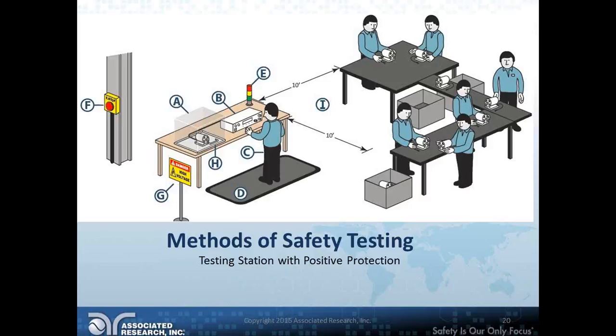You'll also notice what's labeled I, showing a 10-foot spacing from the workstation. That's actually a requirement, meaning if you are not a qualified operator, not trained to work with this equipment, and you're at a station in or near the HIPOT testing station, you must have 10 feet of separation. If you're not trained to work with it, it's 10 feet, bottom line. And OSHA will ding you for that. If you have working stations in or near a HIPOT testing station without that separation, or at the very least other types of PPE, if you're within that 10 feet, you're required to have PPE to protect your operator.